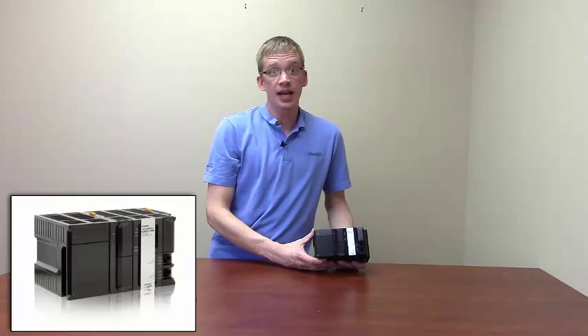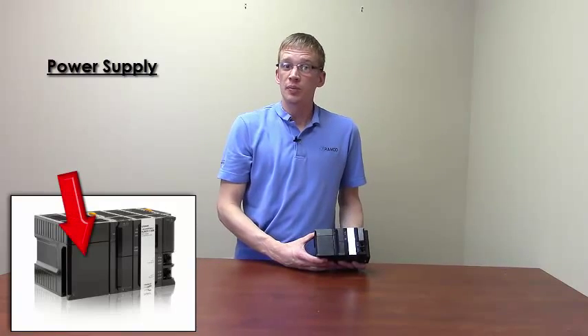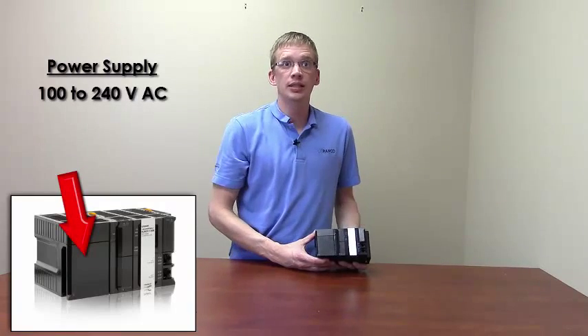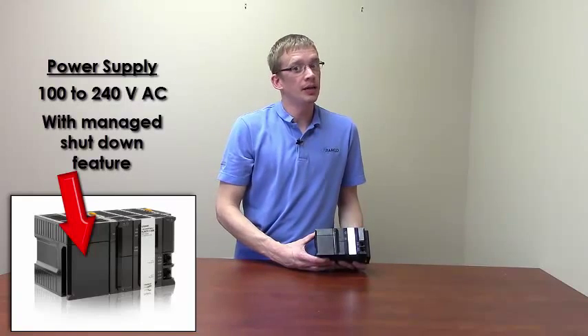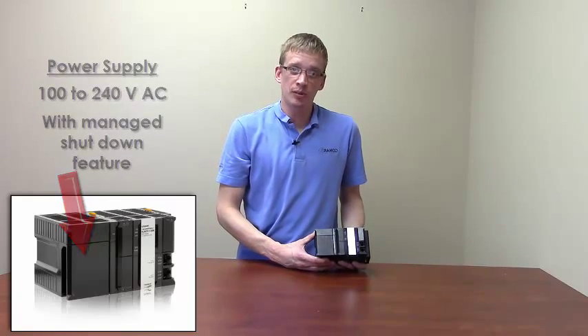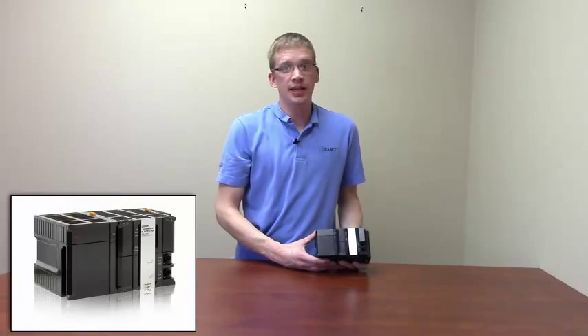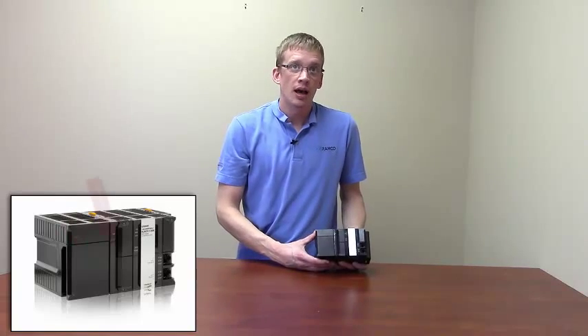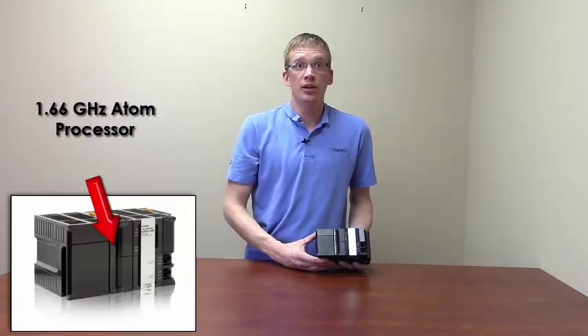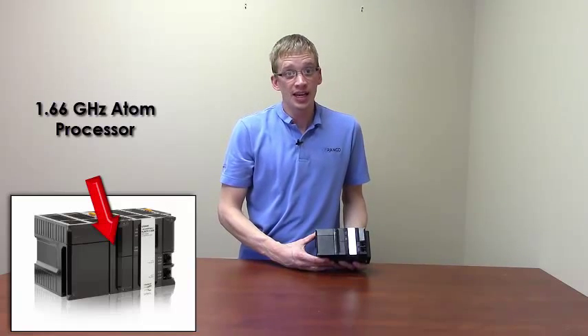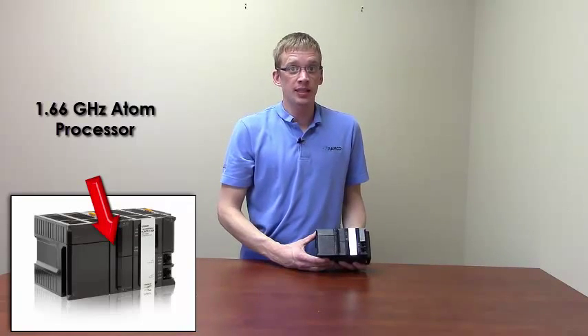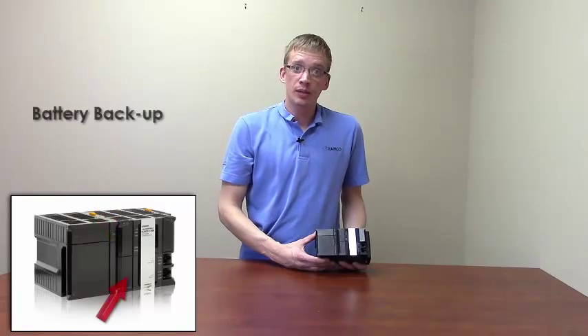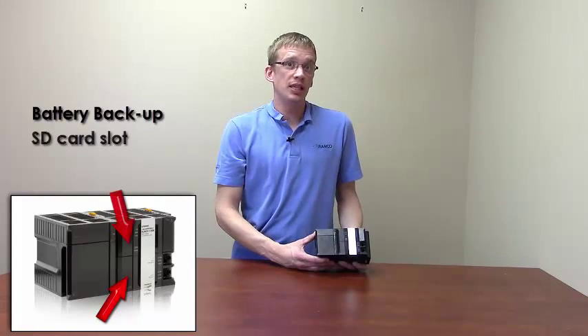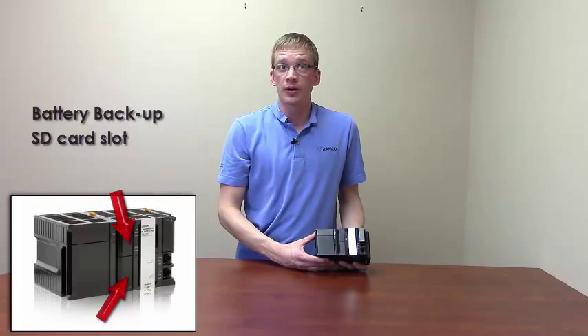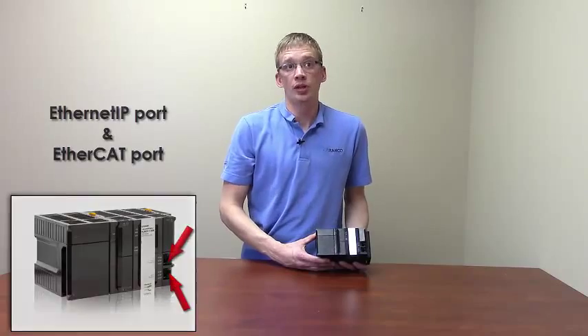On the left-hand side, I have my power supply. It's going to be rated between 100 to 240 volts AC, and it's also managed shutdown. Basically, this means it'll keep power into the processor until it can safely shut down when power is disconnected. I have a 1.66 gigahertz Atom processor, which packs high speeds for multiple axes of motion, battery backup for non-volatile memory, SD card slot for backup and restore, as well as built-in Ethernet IP and EtherCAT ports.